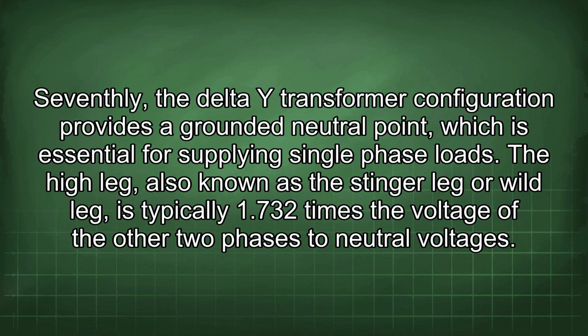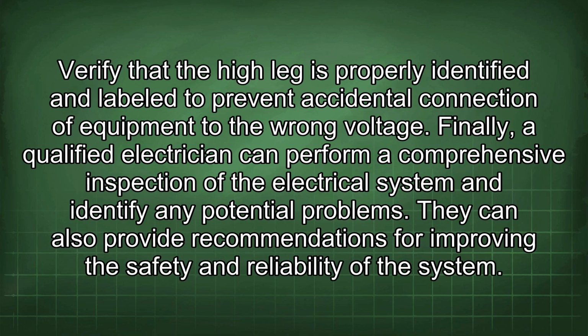Seventhly, the delta Y transformer configuration provides a grounded neutral point, which is essential for supplying single-phase loads. The high leg, also known as the stinger leg or wild leg, is typically 1.732 times the voltage of the other two phases to neutral voltages. Verify that the high leg is properly identified and labeled to prevent accidental connection of equipment to the wrong voltage.